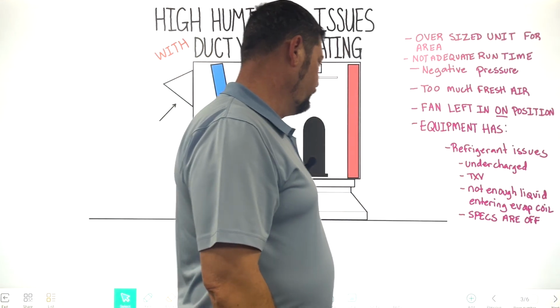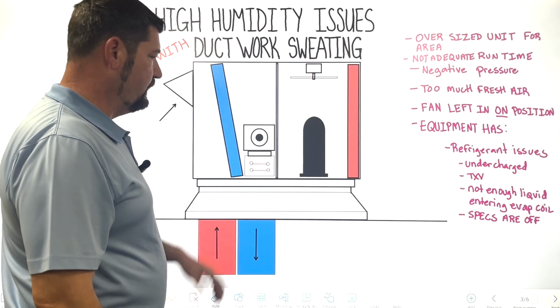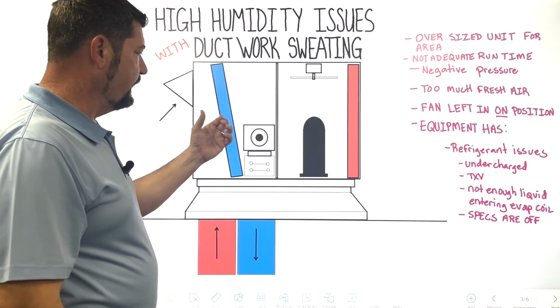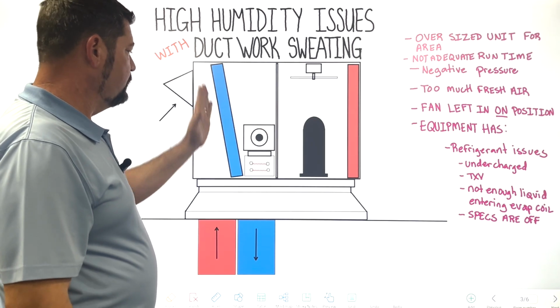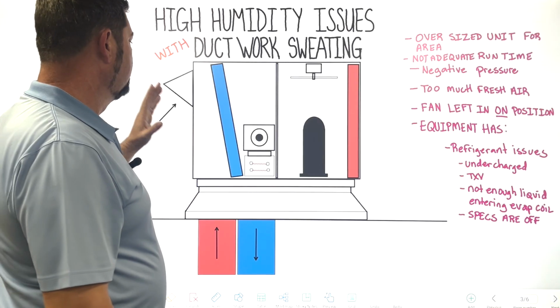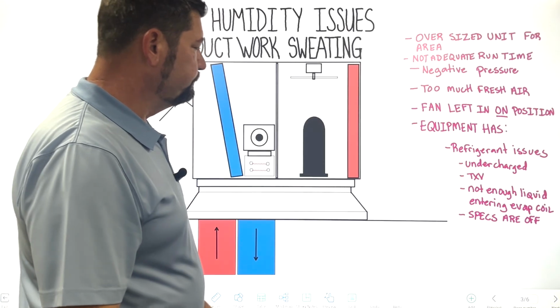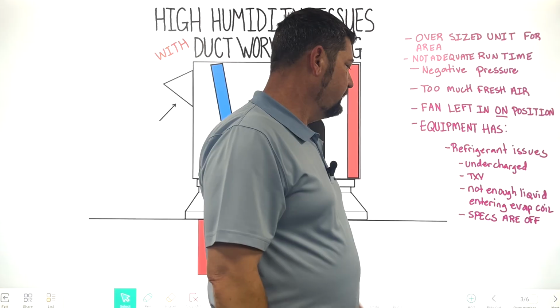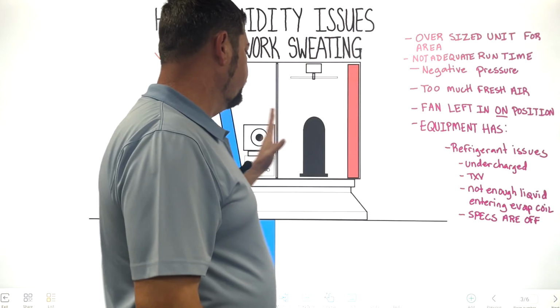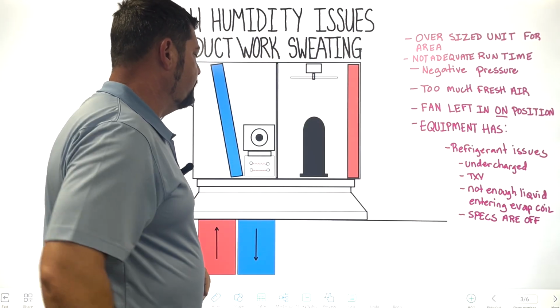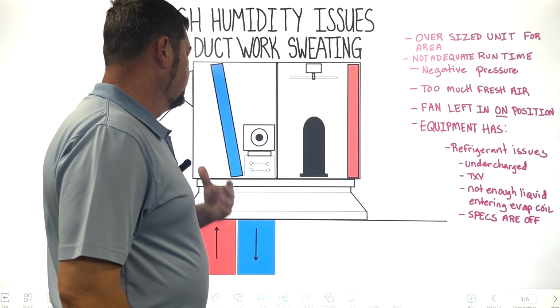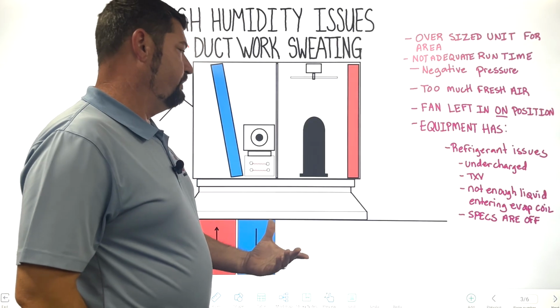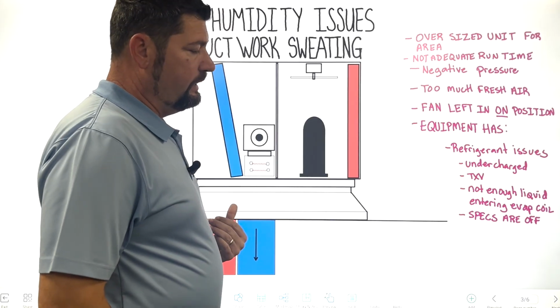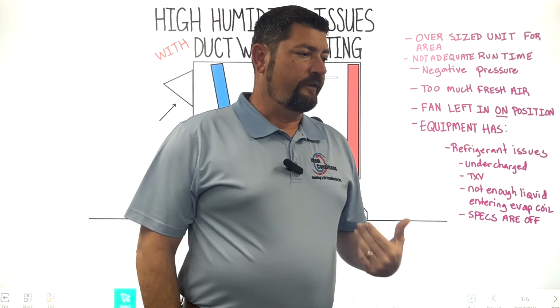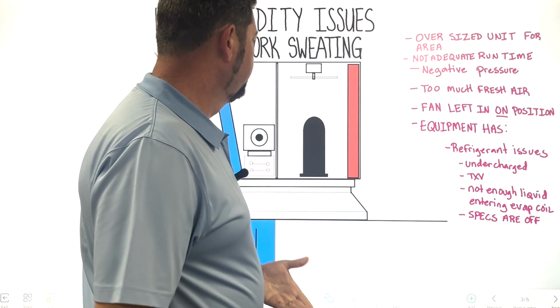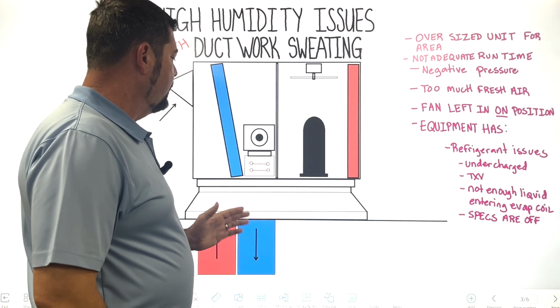We can have expansion valves that meter refrigerant to the evaporator coil, not regulating enough liquid refrigerant into the coil to get the temperature down enough to where that moisture can be removed. Not getting enough liquid entering the evaporator coil, and just in general, if the specs are off. So say somebody swapped out the motor and they didn't go back with the same RPM, or they're running too high of an RPM, for example. Say they pulled out a half horsepower and they put in a 1 horsepower. They put too much airflow there.